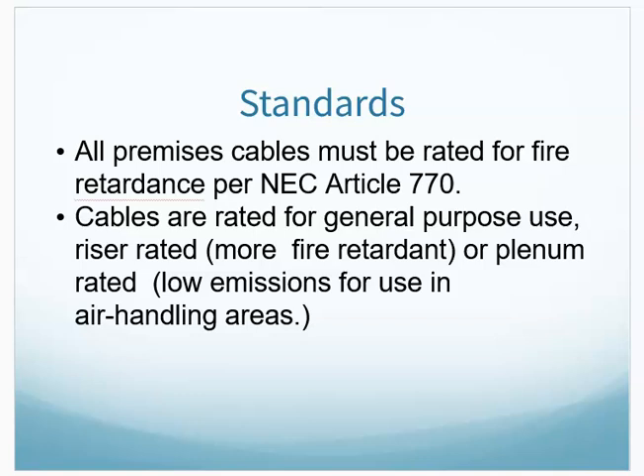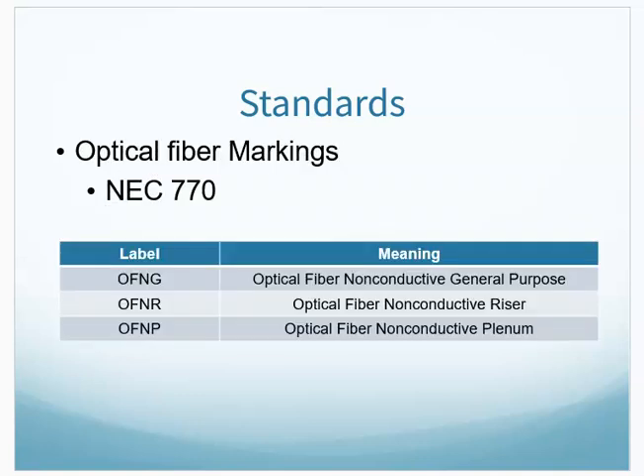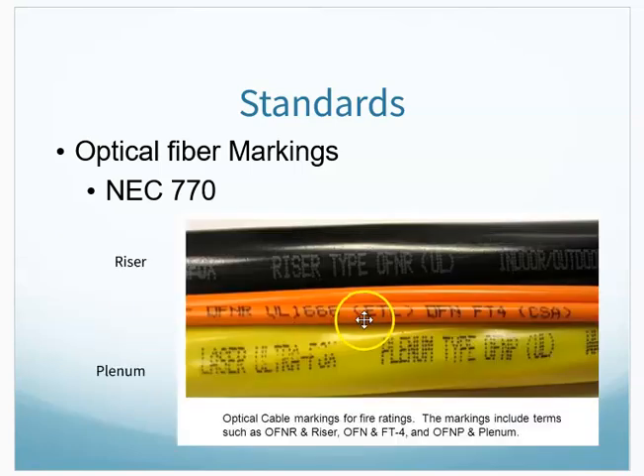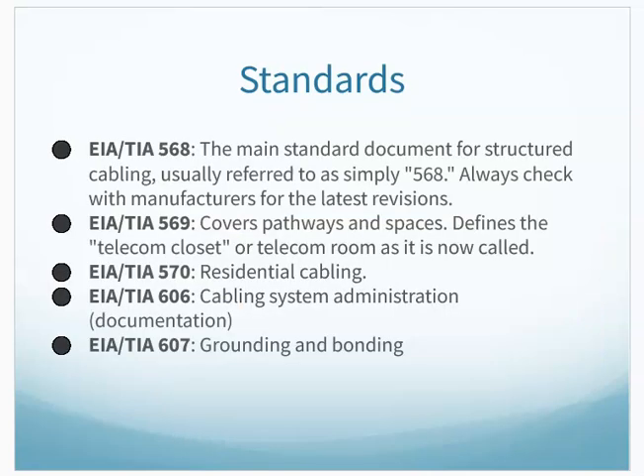Standards also call for fire retardance of the cabling you're installing. Remember the general riser and plenum ratings on fiber optic cable. Looking at the jacket, the last letter tells you the rating: OFNR for riser means that cable can be installed between floors and between closets. OFNP means plenum, which can be installed in plenum spaces above ceilings and so forth. Here's an example of an OFNR riser cable, and here's an OFNP plenum cable.